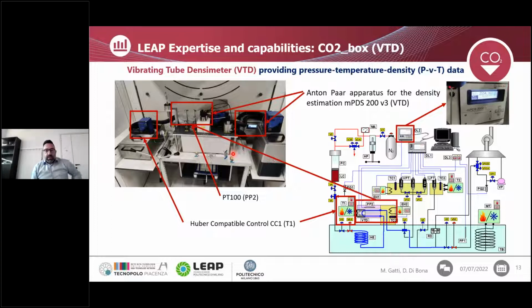So now I start a brief description of the Vdt apparatus. The vibrating tube densimeter is the model DMA112 manufactured by Anton Paar, and the temperature measurements are provided by two platinum probes, PP1 and PP2. In this figure we can see PP2, which is dedicated to the temperature measurement inside the box that contains the U-shaped hollow tube, the core component of this apparatus.